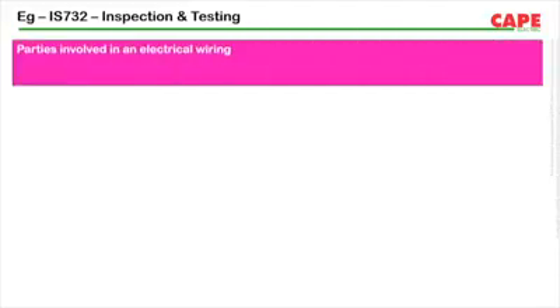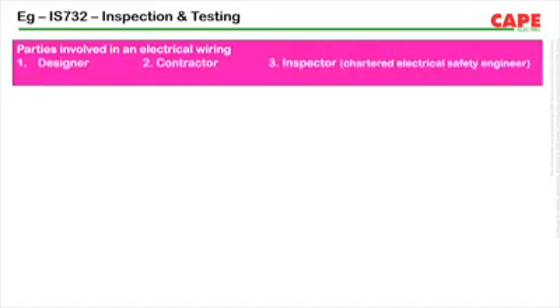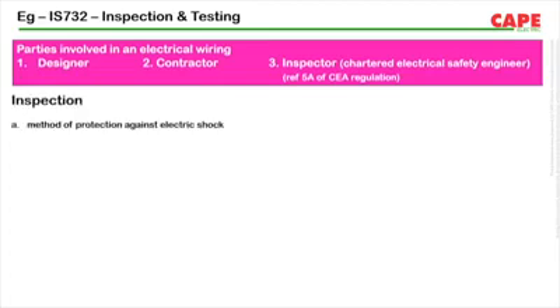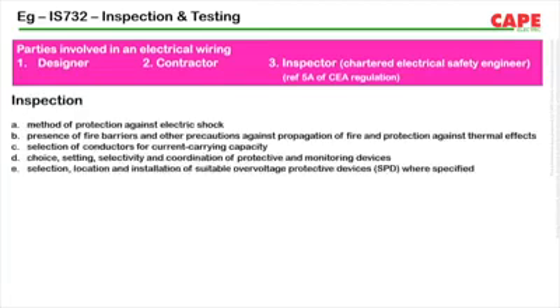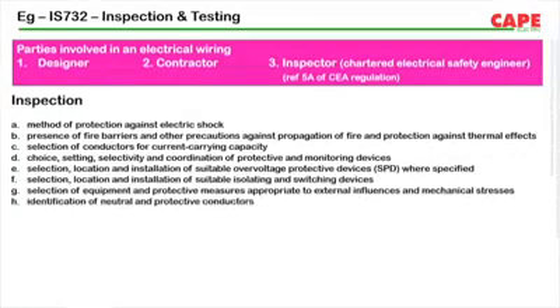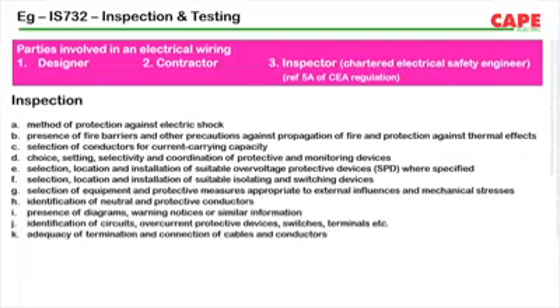Another example of IS 732. There are three people involved in an electrical installation: the designer, the installer, and the inspector. This means the consultant designs the installation, the contractor erects that installation, and the inspector tests that installation. Inspector mentioned here is not the state electrical inspector, but a third-party electrical safety inspector or a chartered electrical safety engineer who is knowledgeable to do the inspection and testing of an installation.